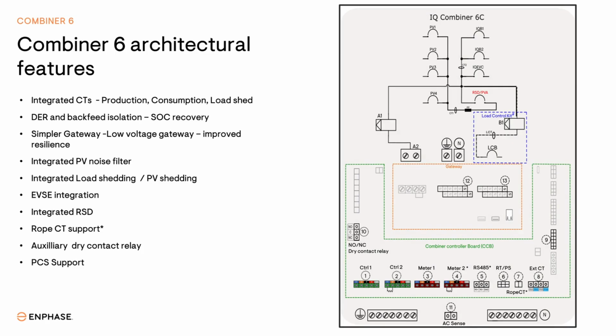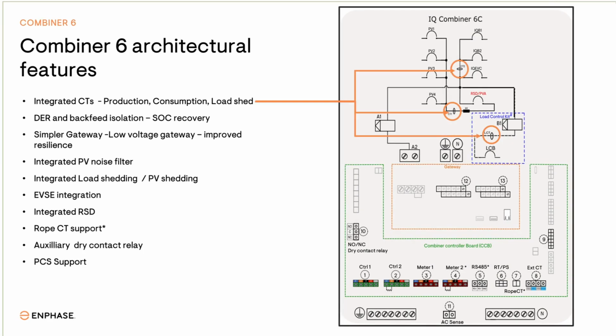One feature of the Combiner 6C for system installers is the integration of CTs directly onto the electrical bus. The integrated production CT and battery CT eliminate the need to install external physical CTs and reduce time and CT metering errors. The built-in load controller also has an integrated CT to provide load metering. When installed with an Enphase IQ meter collar, consumption metering is also included, as the meter collar has built-in consumption CTs. The load control port can also function as a third-party PV or legacy Enphase PV connection port.